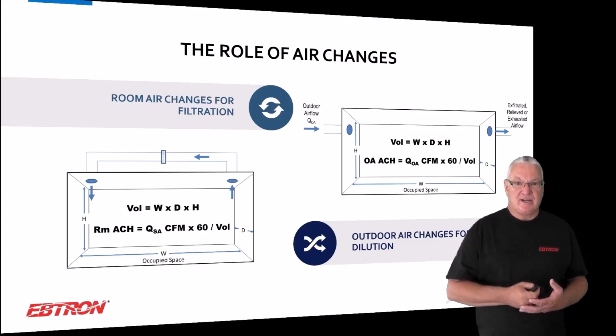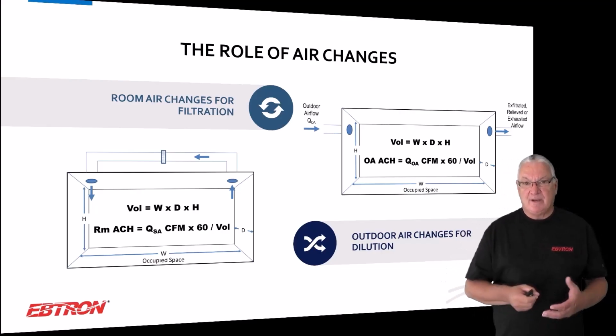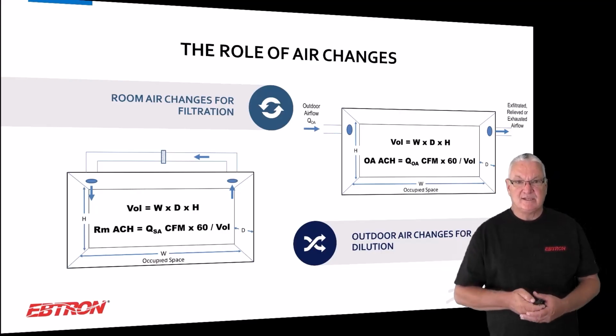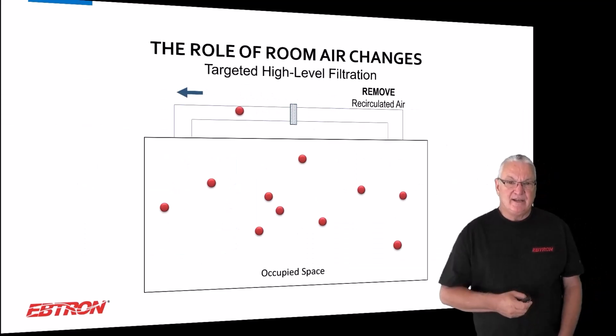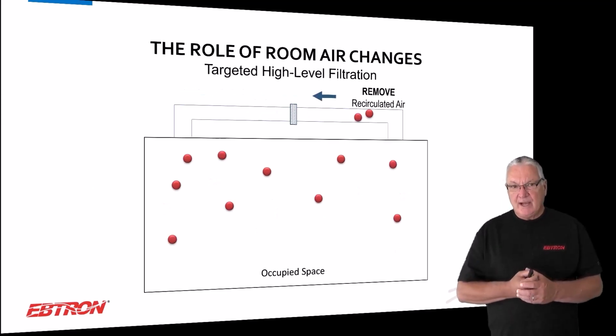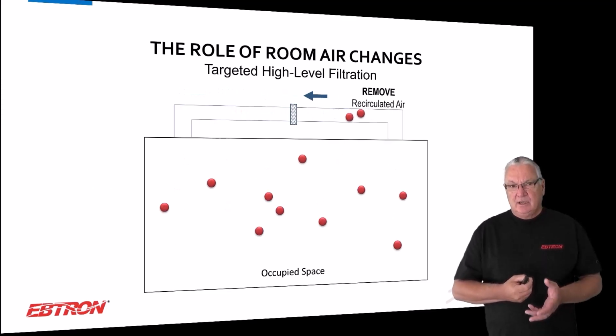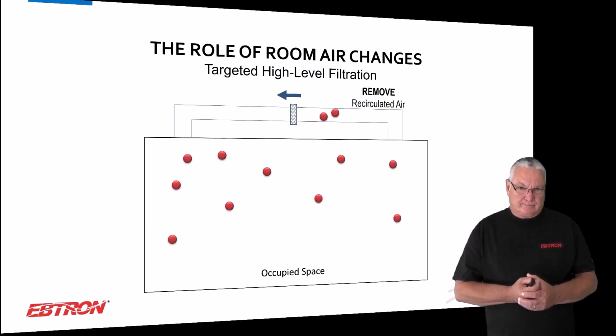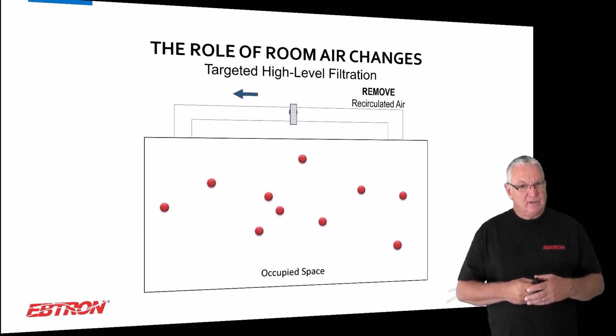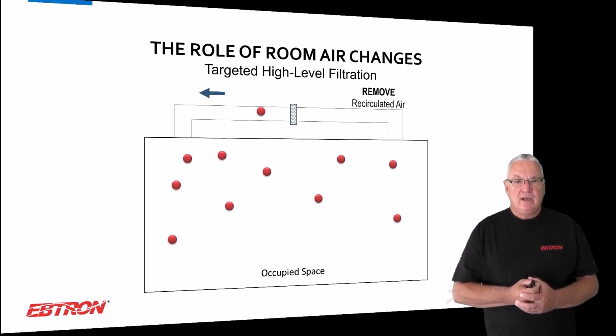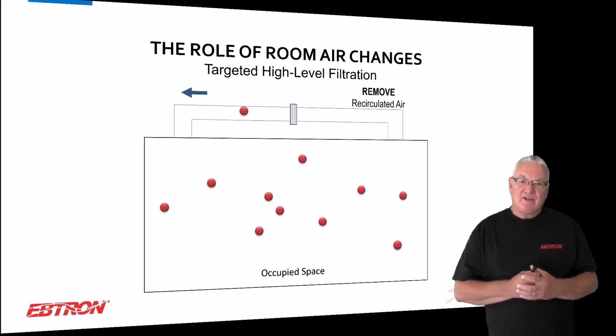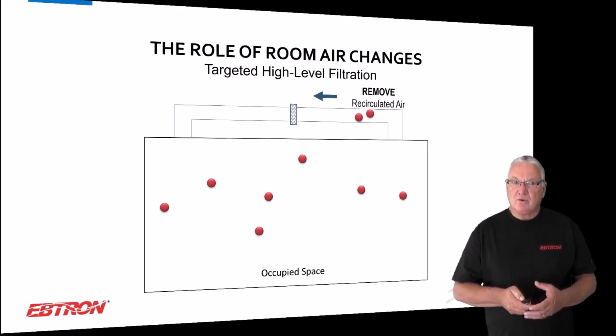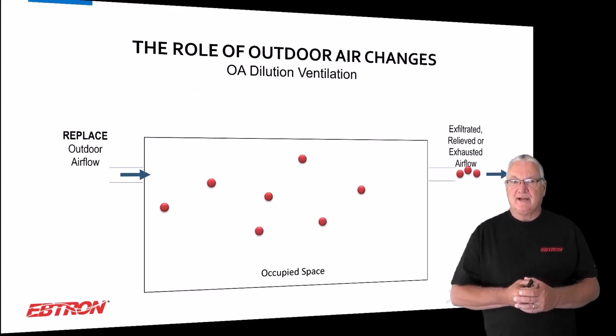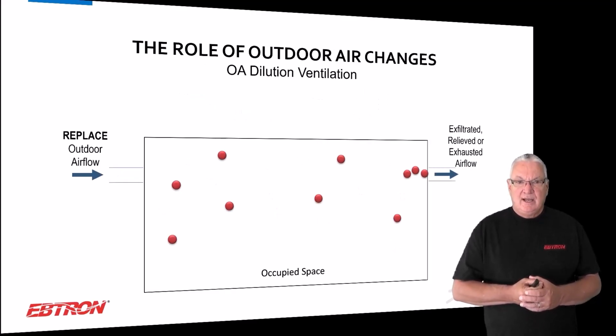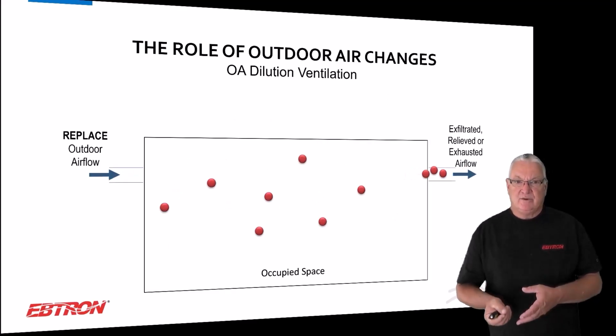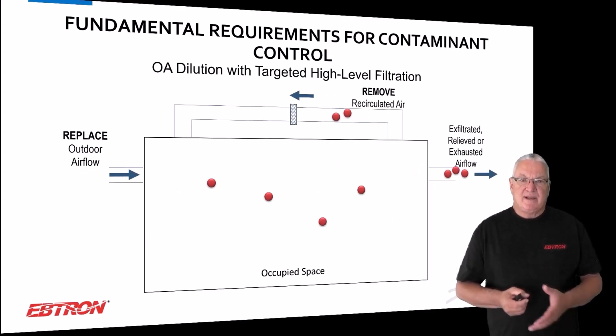And then outdoor air changes is all about dilution. How many times do we dilute out the space? And so when you take a look at it, you have filtration, okay? And we can remove a lot of contaminants with filtration, but typically speaking, filtration alone isn't going to do it all. So we also talk about outdoor air changes for dilution. And so again, outdoor air isn't going to do it all either. So it's a combination of the two.